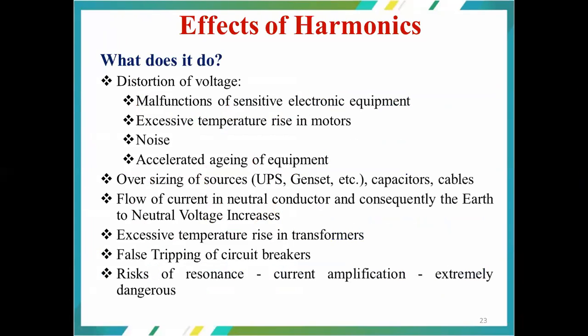And the effects of harmonics: the first thing is the distortion of the voltage. The voltage waveform is going to get distorted, which leads to malfunctions of sensitive electronic equipment, from medical devices to EVs or any larger electric motor drives. Then there is the excessive temperature rise in the motors. As I already mentioned, with the fundamental component we have reduced iron losses, whereas with other harmonic components you have increased iron losses. Thereby, you have excessive temperature rise in the motors, and also noise, that is, disturbance in the machine operation.